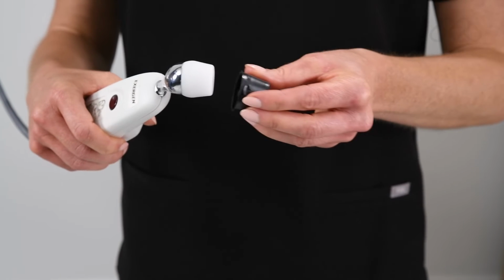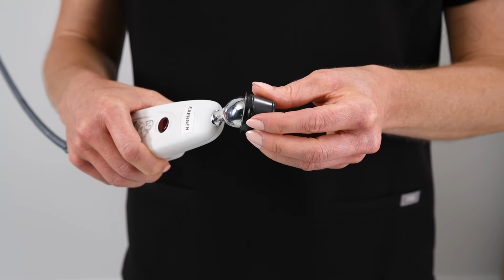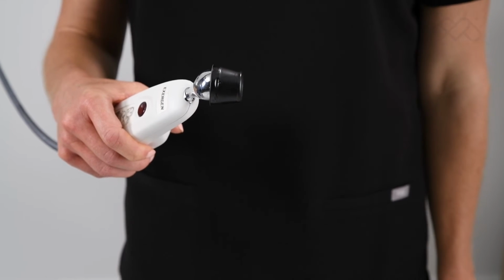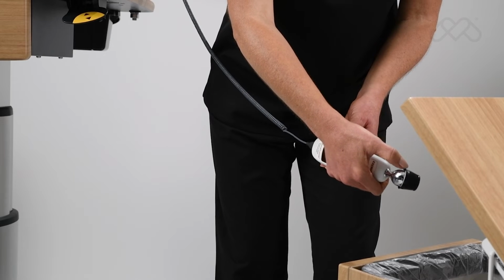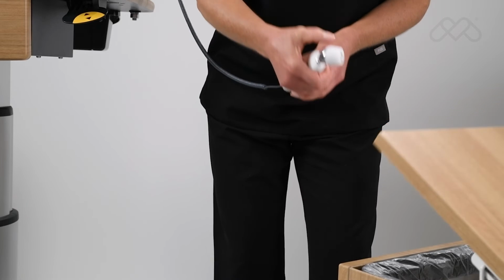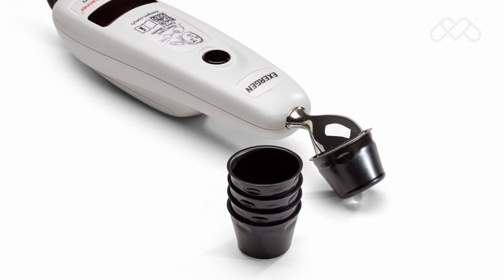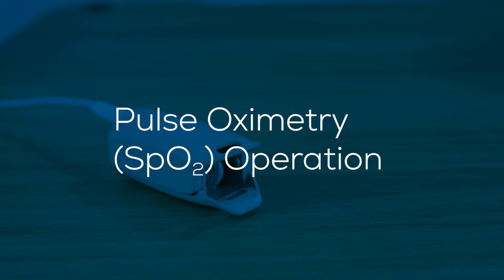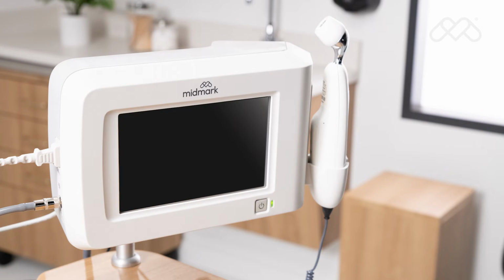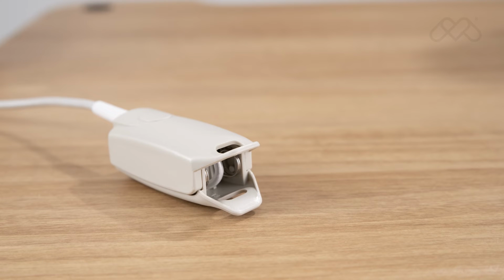To use the disposable caps, apply the cap by pushing it onto the probe cone with the fingers. Remove the cap by pushing the top edge of the cap forward with the thumb. Caps may be reused on the same patient. Pulse oximetry (SpO2) operation.